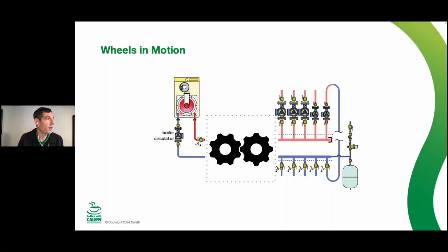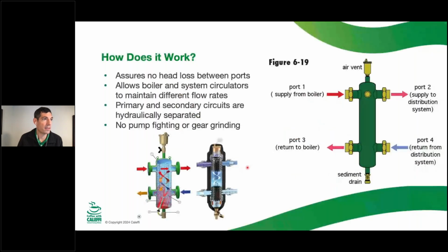We want to make sure that the left side of this equation is getting exactly the flow rate that it needs, and that's why we're going to split this with primary secondary. So the simplest way for me, at least, to think of primary secondary is we just are separating the wheels. We just are moving the gears away from each other so they're not in conflict anymore. So this could be 1,000 GPM, this could be 4 GPM, and they don't fight each other. That's what primary secondary needs to do.